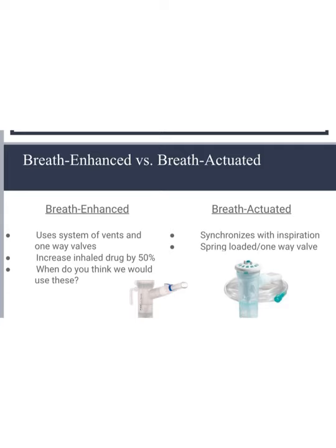So we would use these with CFers, and we would use them to encourage patients to get as much drug as they can. The reason that these aren't used all the time at every single patient at every single hospital is because they are a lot more expensive than the typical small volume neb. So at home, these are used with a compressor. That way they have the proper particle size. The baffle is different in these, in the middle, and I'll show you on our video. The baffle is bigger, so it's going to make the particle sizes even smaller.